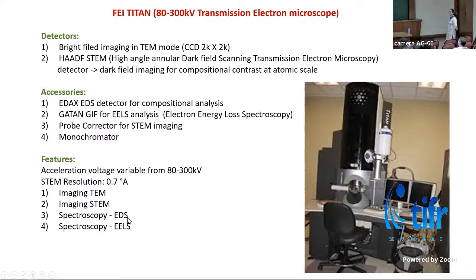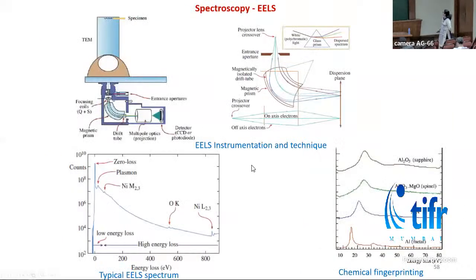It has an electron energy loss spectrometer for detecting elements present in the sample. Basically, EELS is used for detecting low Z elements, which cannot be done very efficiently using EDS. So this is the EELS spectrometer. When the electron beam passes through the sample, it loses some amount of energy. And if we can measure that energy loss, then we can identify the elements present in the sample.